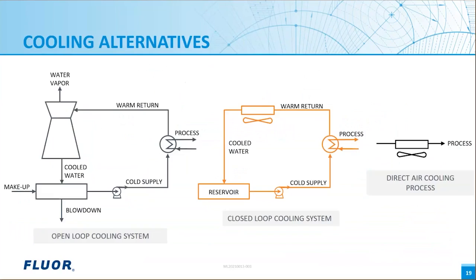Here's an example of a few cooling alternatives to reduce water consumption. As discussed earlier, a significant water demand in many plants is cooling water makeup. This sketch illustrates the three potential configurations that are possible for cooling. The open loop cooling system on the left is advantageous in that it provides the lowest cooling medium supply temperatures, a relatively small footprint for overall cooling duty, and it results in smaller heat exchangers in the process units, at the expense of evaporated water.